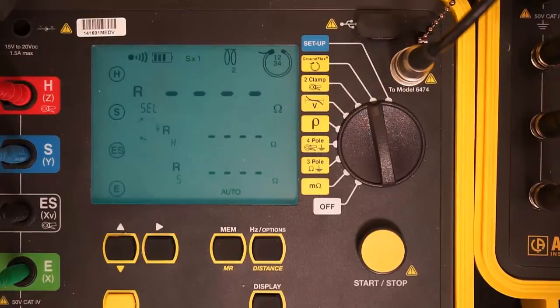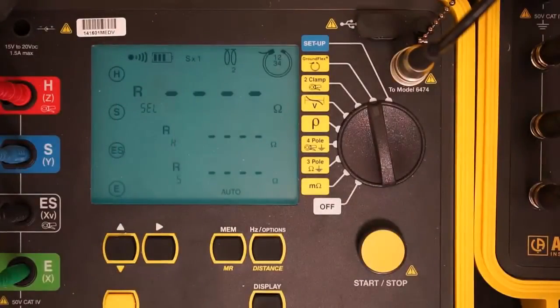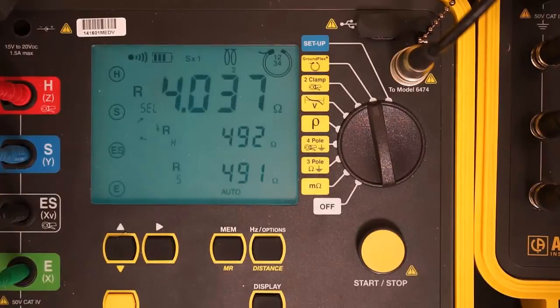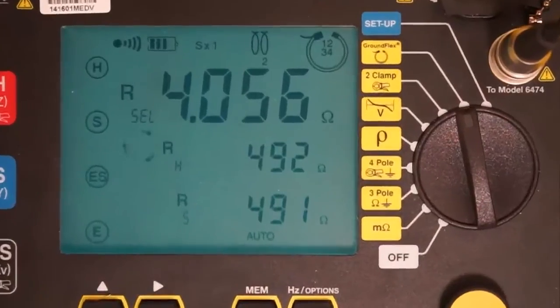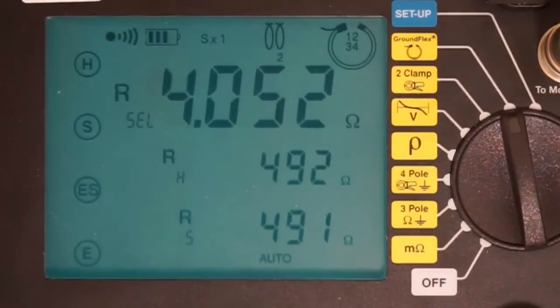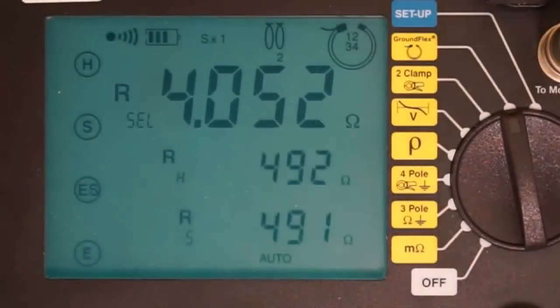During this process, an indicator consisting of 3 rotating arrows appears. This remains on the screen until the instrument completes its measurements and calculations and displays the results. When this process is complete, the values are displayed. At the top of the screen is the total tower resistance. In our test, this is the resistance for the combined 4 tower legs, which is around 4 ohms. A properly grounded tower should produce a measurement below 15 ohms and ideally below 5 ohms.